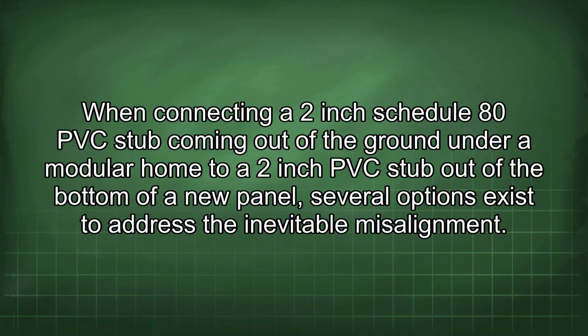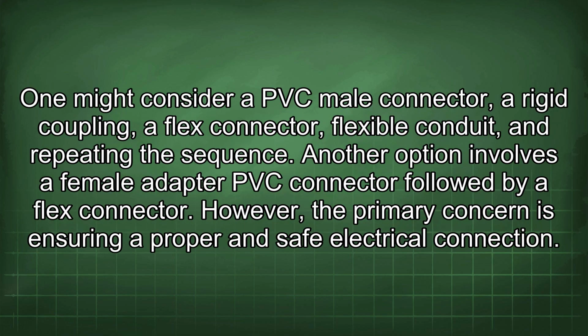When connecting a 2-inch Schedule 80 PVC stub coming out of the ground under a modular home to a 2-inch PVC stub out of the bottom of a new panel, several options exist to address the inevitable misalignment. One might consider a PVC male connector, a rigid coupling, a flex connector, flexible conduit, and repeating the sequence. Another option involves a female adapter PVC connector followed by a flex connector.